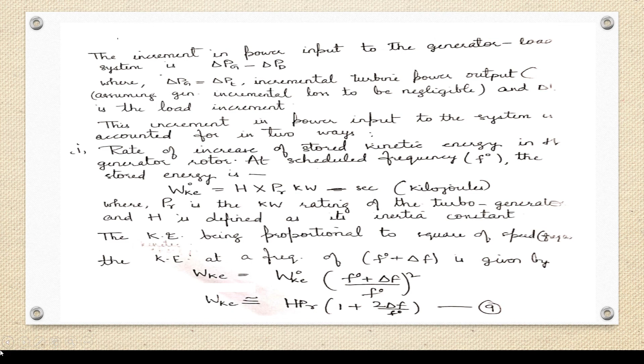Rate of change of kinetic energy can therefore be written as d by dt of Wke, that is 2 H PR by F naught d by dt of delta F. Now let us see the second condition. As the frequency changes, the motor load changes. Being sensitive to speed, the rate of change of load with respect to frequency, that is dou Pd by dou F, can be regarded as nearly constant for small changes in frequency delta F, and can be expressed as dou Pd by dou F into delta F equal to B delta F, where the constant B can be determined empirically and B is positive for a predominantly motor load.